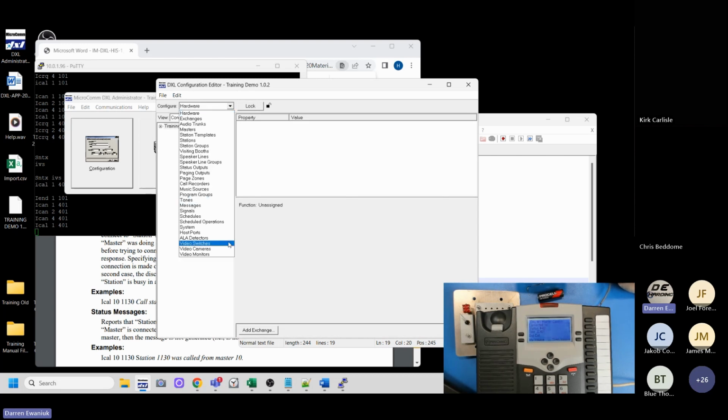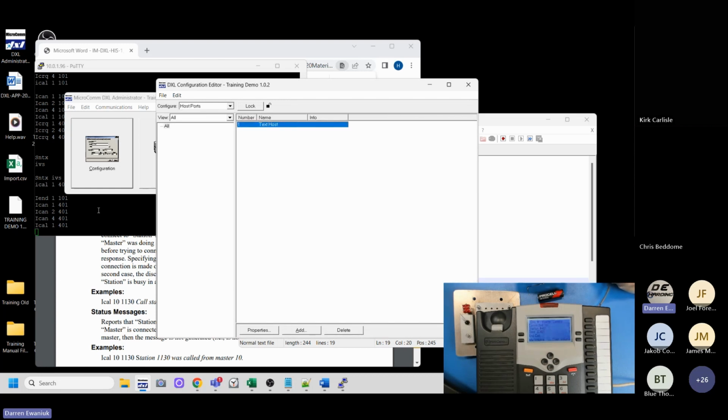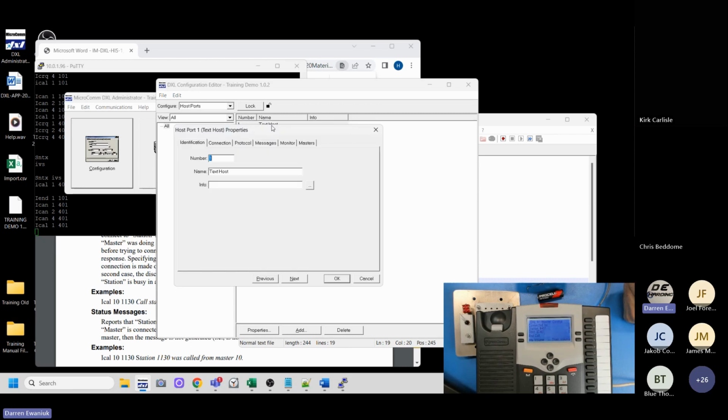So if you have a DXI system that you are upgrading to a DXL, part of the host interface specifications tells you exactly what I'm going to show you. Basically, if you want to ensure DXI compatibility, so that you're changing from a DXI system to a DXL system and you're not changing your control system, you can disable the new DXL commands and it will revert to the old DXI commands.